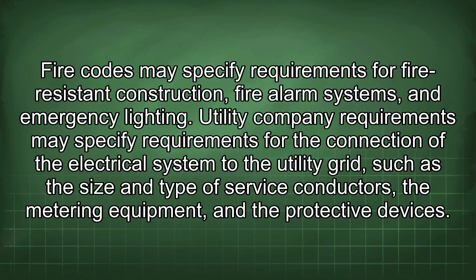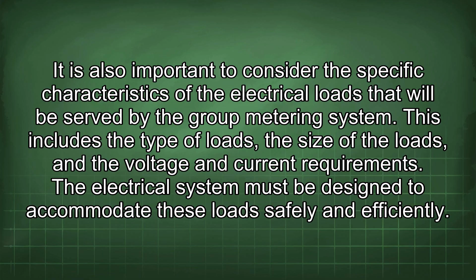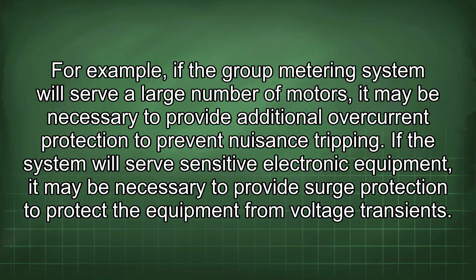It is also important to consider the specific characteristics of the electrical loads that will be served by the group metering system. This includes the type of loads, the size of the loads, and the voltage and current requirements. The electrical system must be designed to accommodate these loads safely and efficiently. For example, if the group metering system will serve a large number of motors, it may be necessary to provide additional overcurrent protection to prevent nuisance tripping. If the system will serve sensitive electronic equipment, it may be necessary to provide surge protection to protect the equipment from voltage transients.